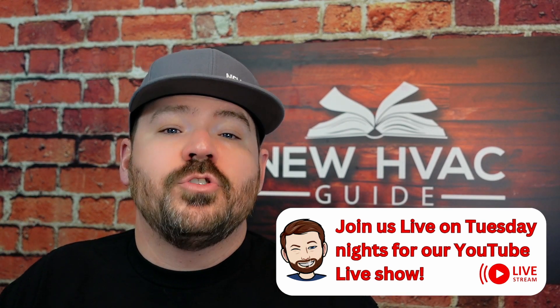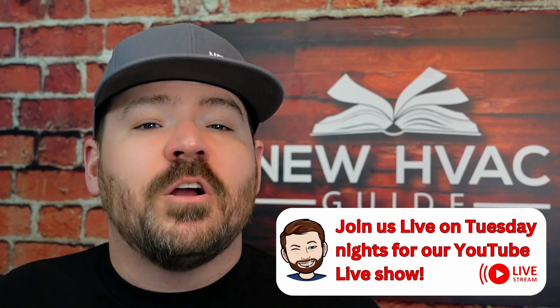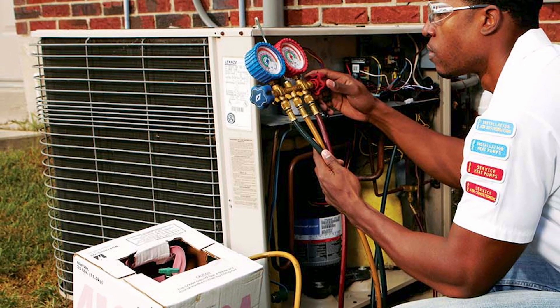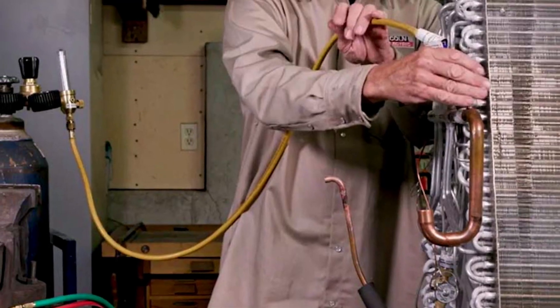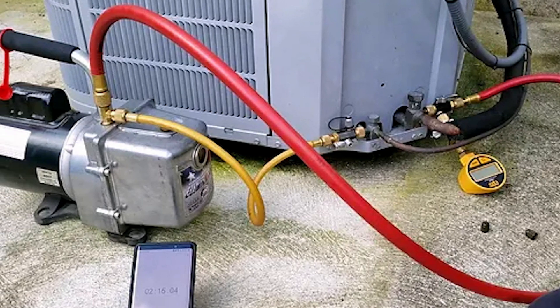It's very important to do your best to get rid of these problems or alleviate them before they start. Now let's talk about why the acid is there. A large majority of heating and air systems have oils in them that react to other things. That's why people who do this correctly are always making sure things are clean — pulling good vacuums, purging with nitrogen, doing triple evacuation, all the things we can do to get that system nice and clean. When there are contaminants or moisture in that system, these oils become acidic.